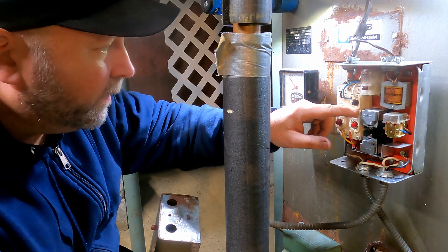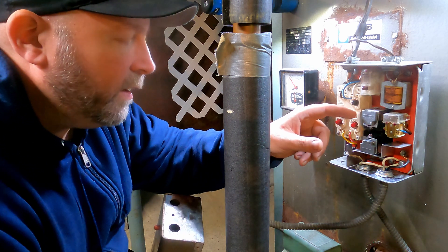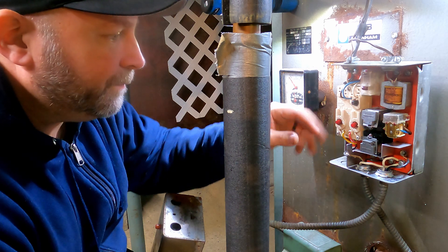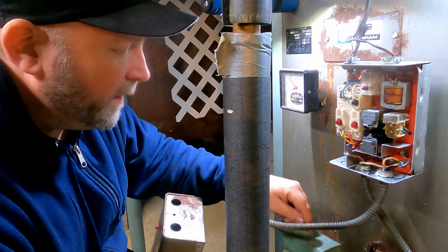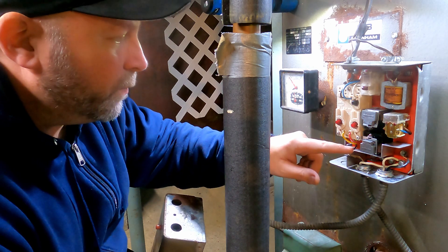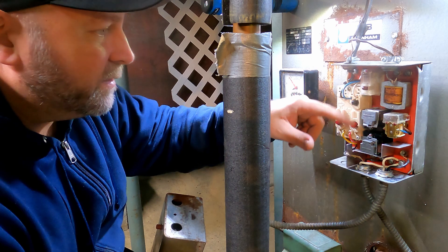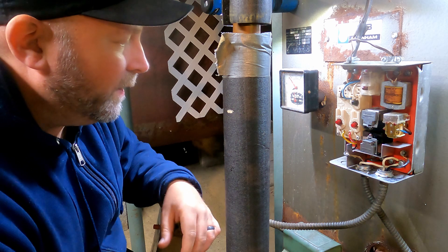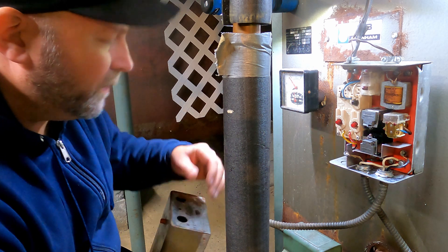What's going on here: it's powered off, the contact for the furnace isn't working. The one for the circulator down here is tripping, working fine. But this one here — the reset doesn't do anything. You actually have to physically turn it on manually, and that's no fun. It's just gave up the goose.